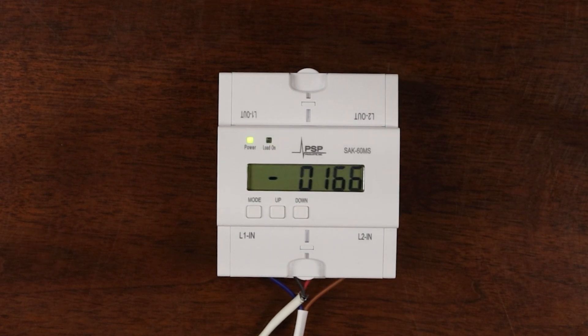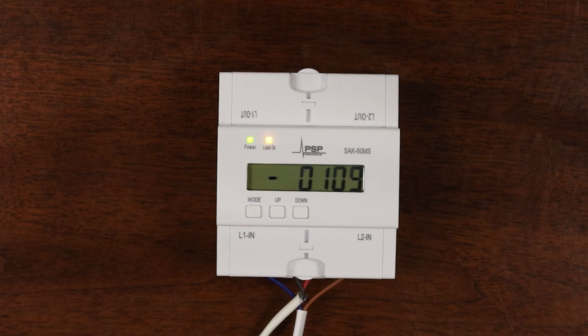And then when the current finally drops below 115 amps, then it will close to restore the load. And that's it. That's how it works.